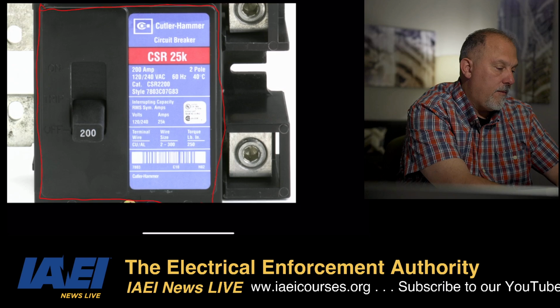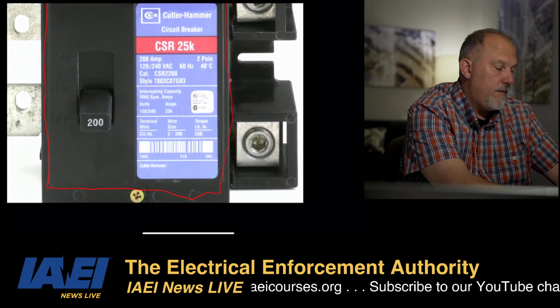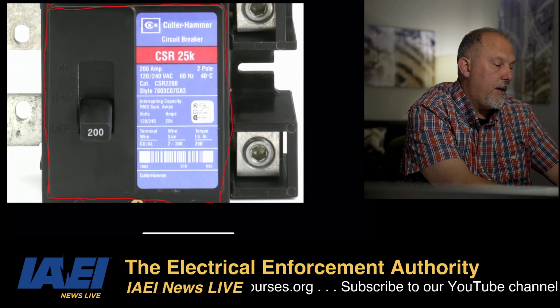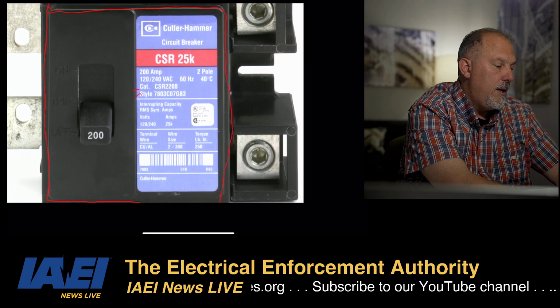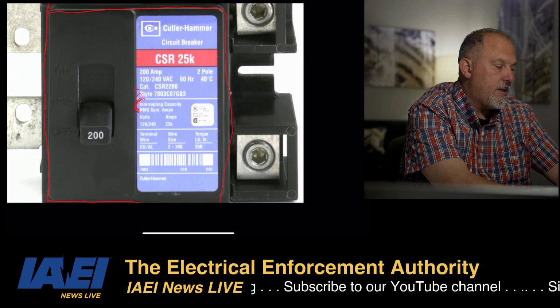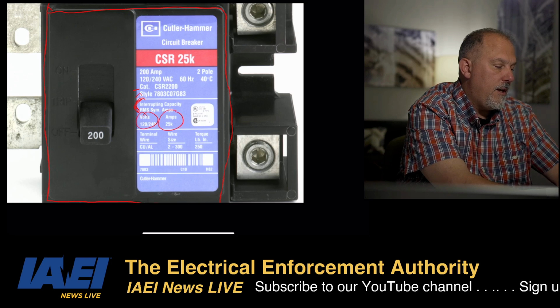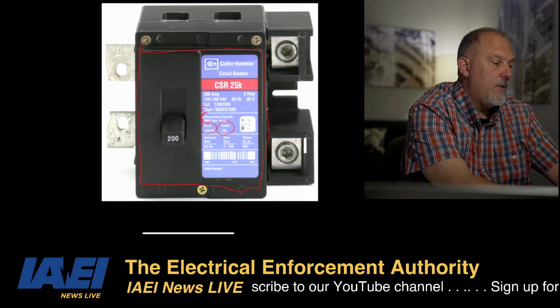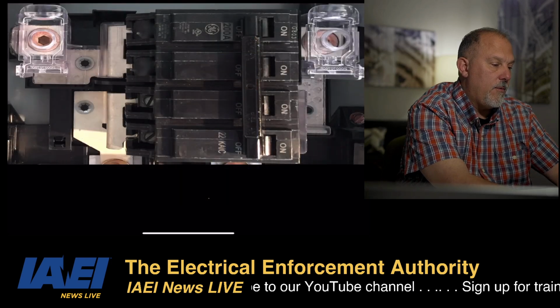Interrupting rating. Where is it? Where is the interrupting rating? I got catalog number, style. Here it is, interrupting RMS. At this voltage, 25,000 amps. So the interrupting rating would be available through the dead front.